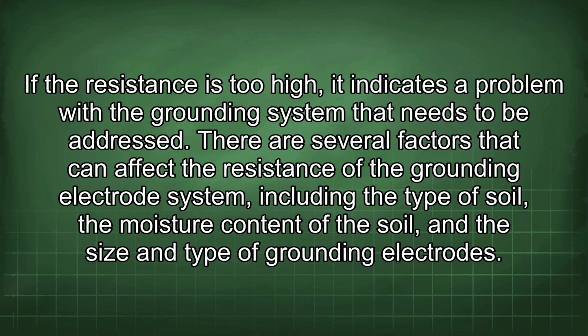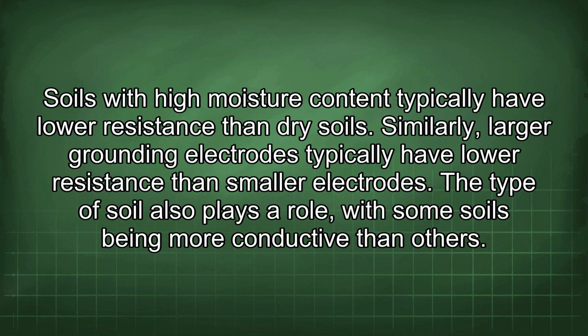There are several factors that can affect the resistance of the grounding electrode system, including the type of soil, the moisture content of the soil, and the size and type of grounding electrodes. Soils with high moisture content typically have lower resistance than dry soils. Similarly, larger grounding electrodes typically have lower resistance than smaller electrodes. The type of soil also plays a role, with some soils being more conductive than others.